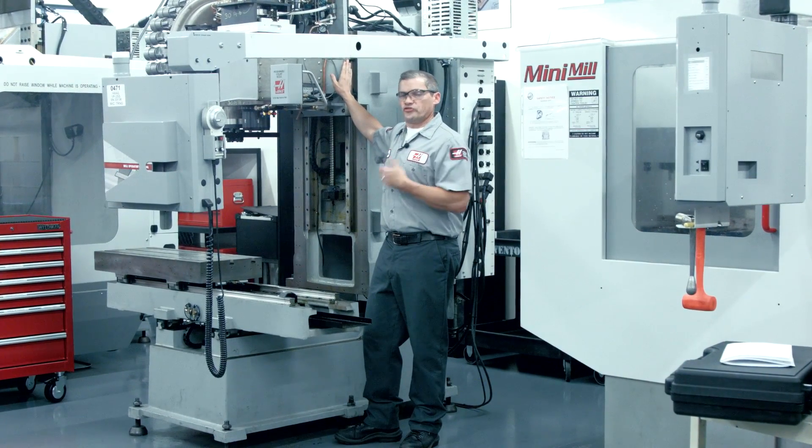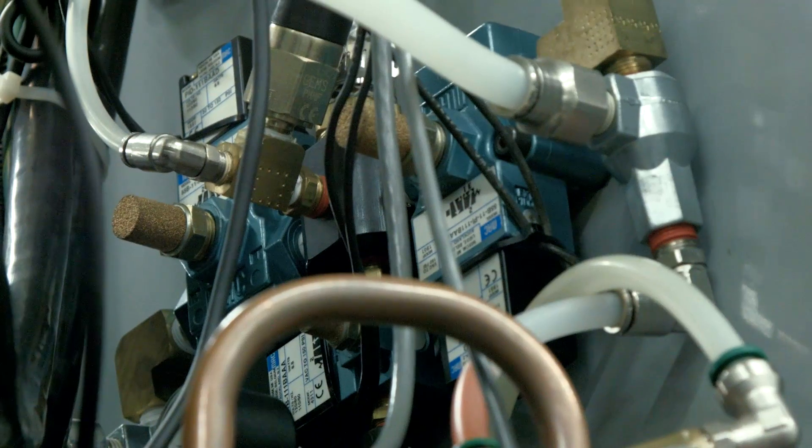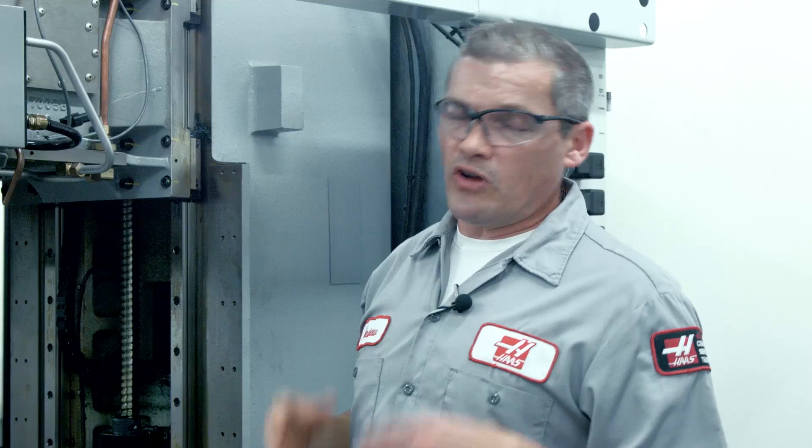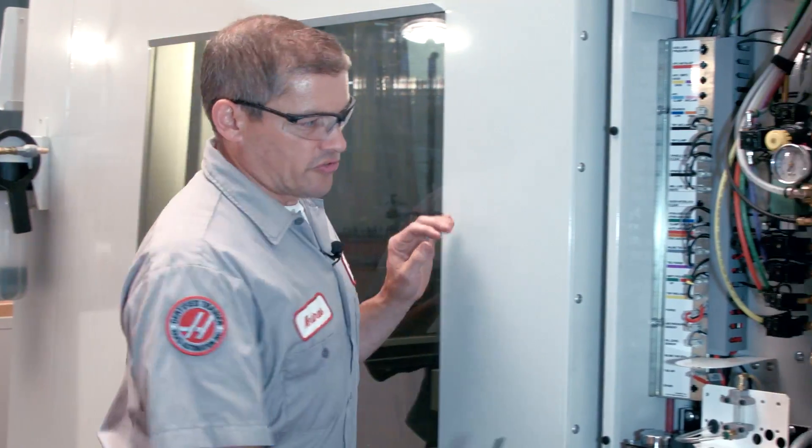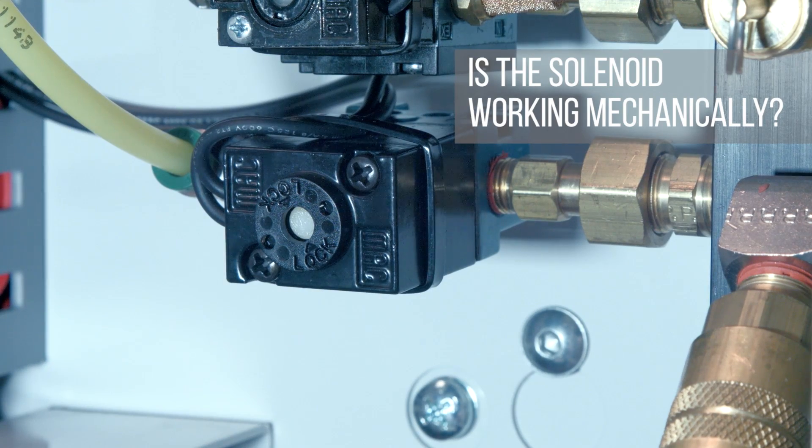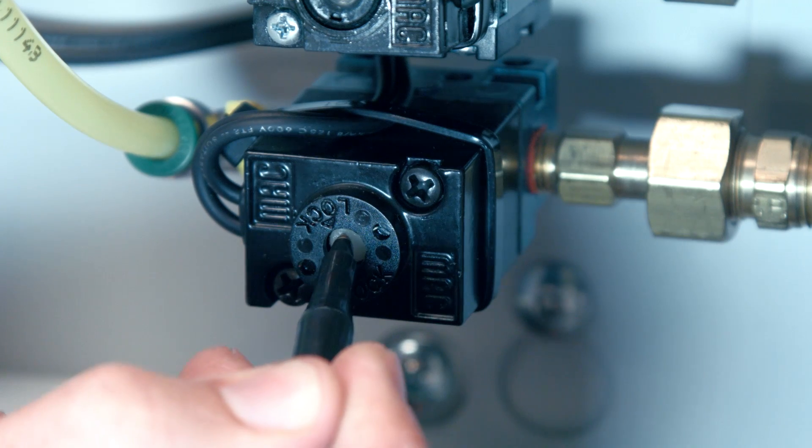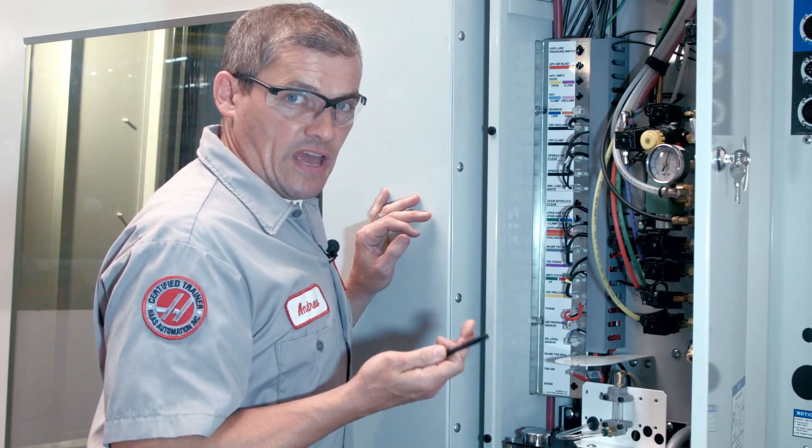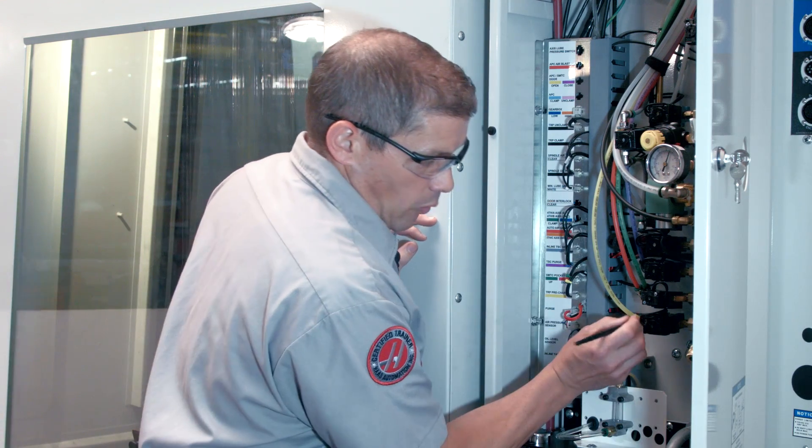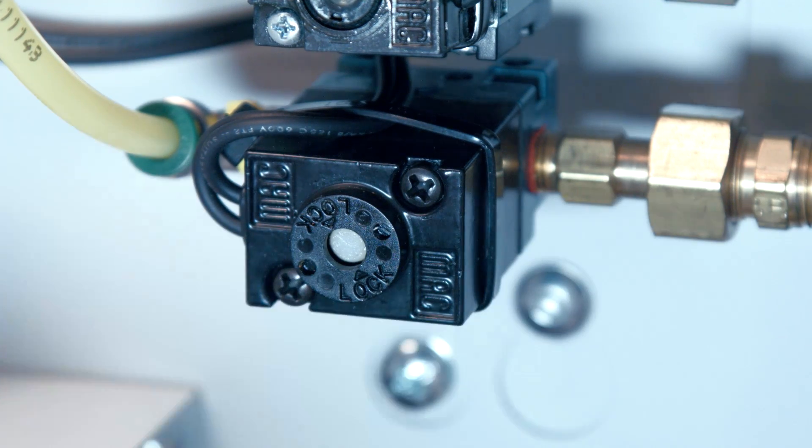So next we're going to move on to checking that this solenoid works correctly mechanically. If you're working in an older machine where the solenoids are not centrally located in the air lube panel, then you need to start by finding the solenoid that you need to test. Once you've correctly located that solenoid the rest of the troubleshooting process is just the same. So we need to check that the solenoid mechanism itself is functioning correctly. Now we'll do that by using the manual override button. When I depress this manually it moves the valve to the open position. And I can use a ballpoint pen or the round end of a hex wrench.